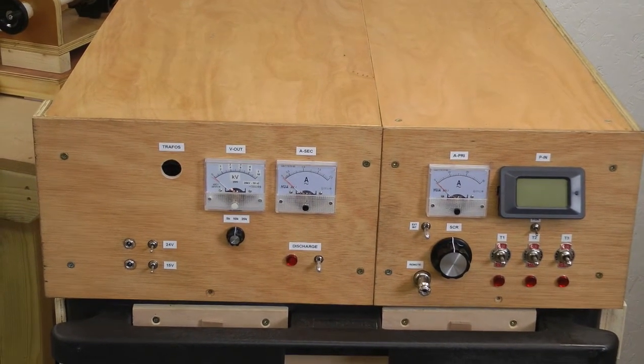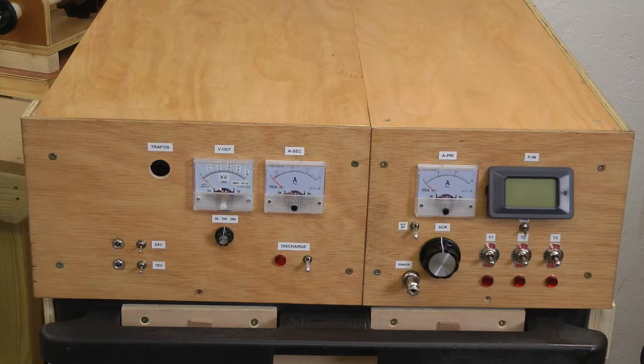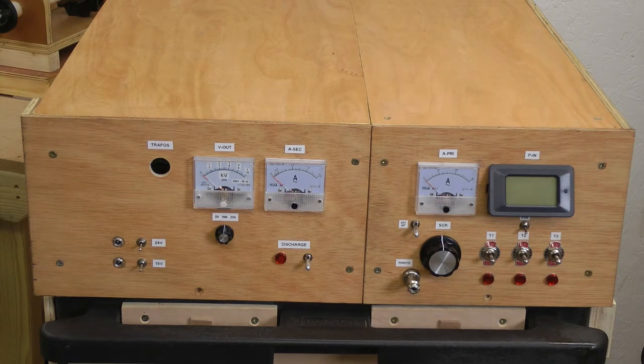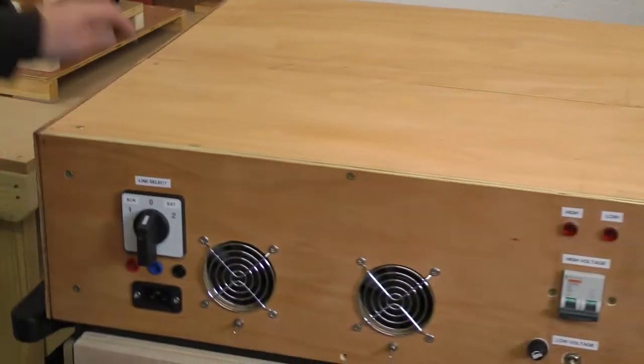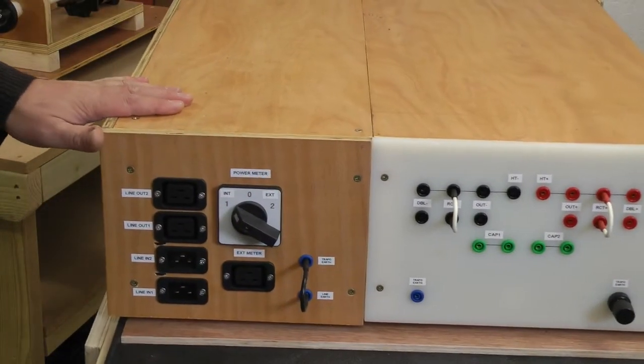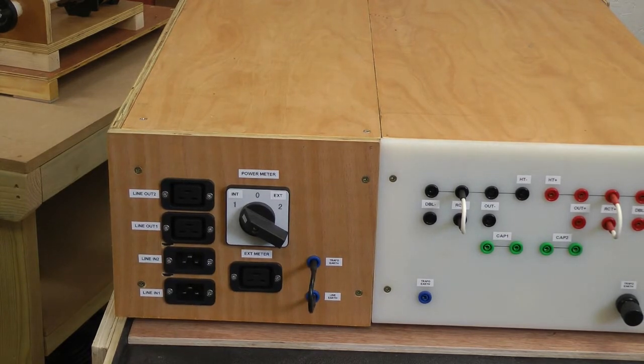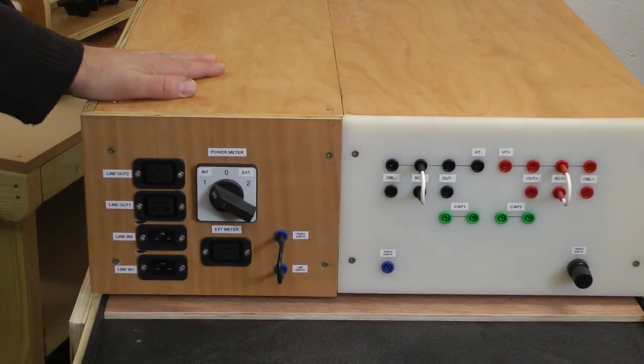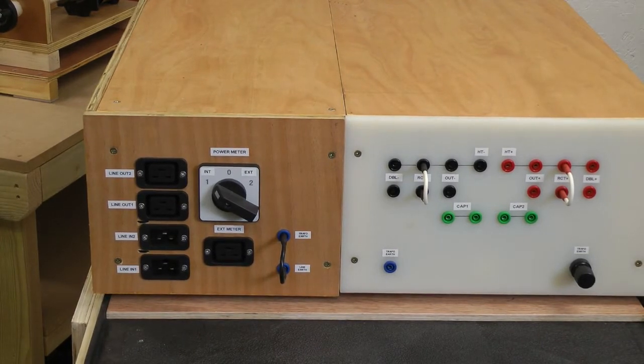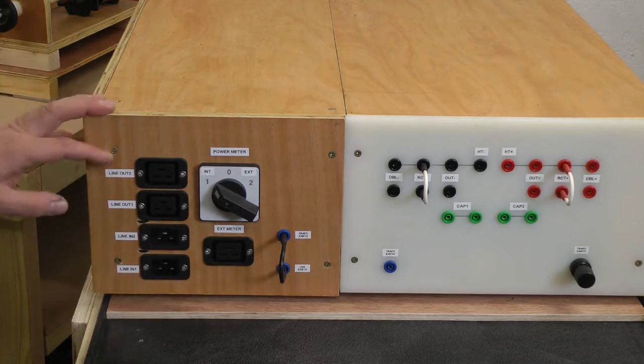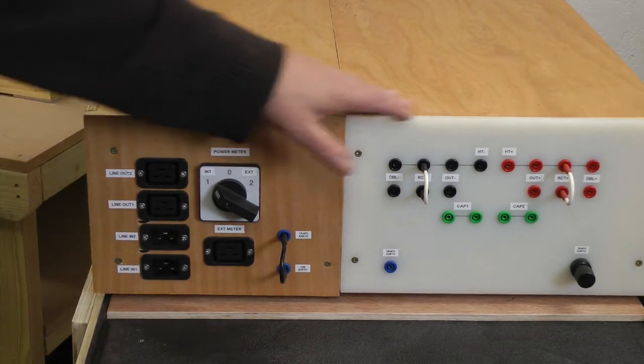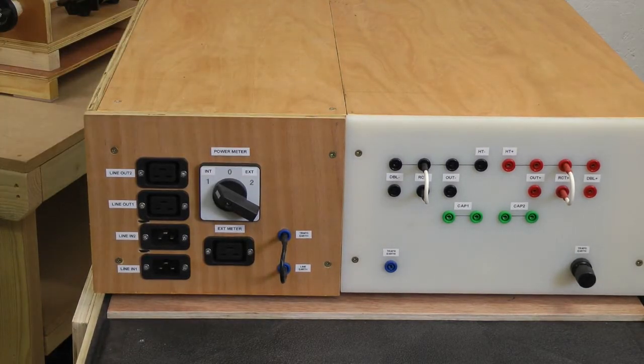Okay, so the core of this unit is basically the high voltage transformers. It uses 3 industrial microwave oven transformers, so each of those is a 1.8 kVA transformer. So if I actually start from the back, I'll just check that's in view of the camera. About there. Okay, so this is our mains input, output and control board. This is the high tension output. It's made on a nylon board. Obviously there can be quite high potentials in there.